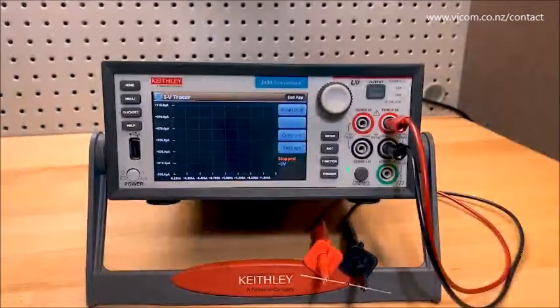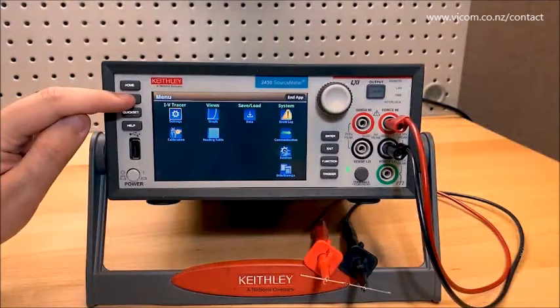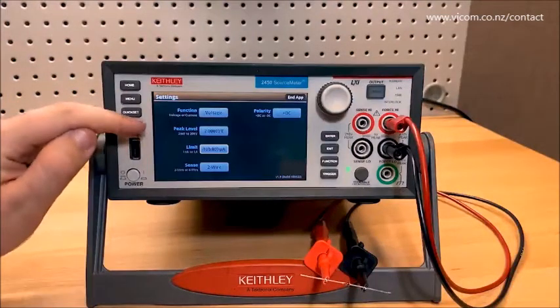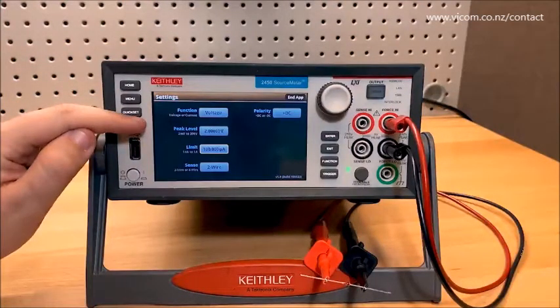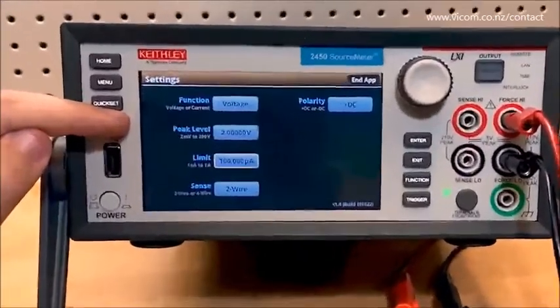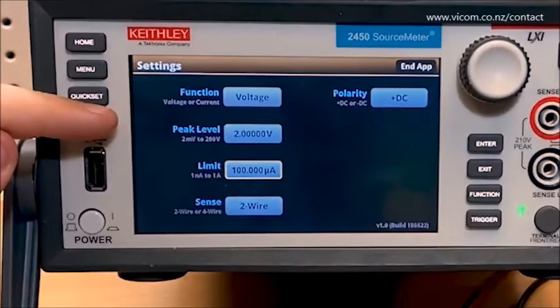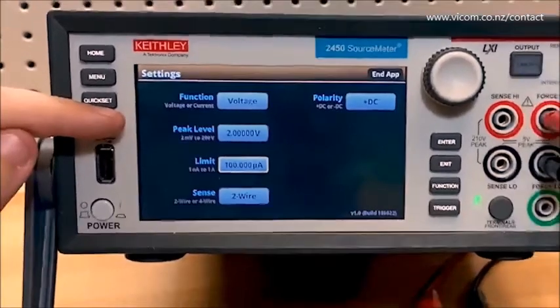I want to show you the settings screen and different polarities now. Going to the menu button, you can see the menu screen is completely different from normal. This settings screen holds most all the settings you'll care about, and there's a shortcut to get here from the main screen. You can see there are settings for outputting either voltage or current, the peak output level, measurement limits — effectively the power limit — selecting two-wire or four-wire sense, and the polarity setting.